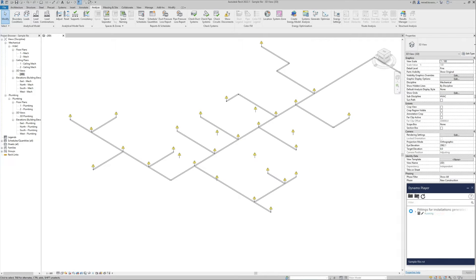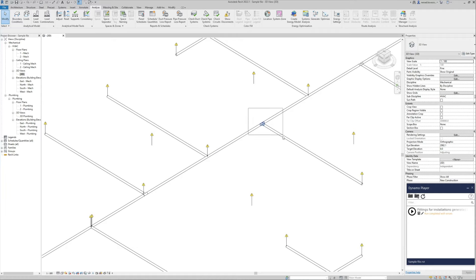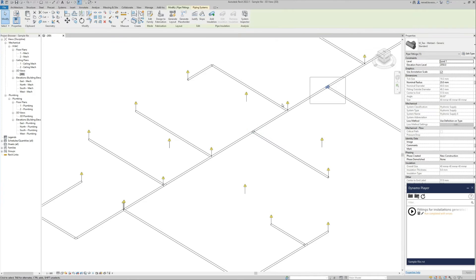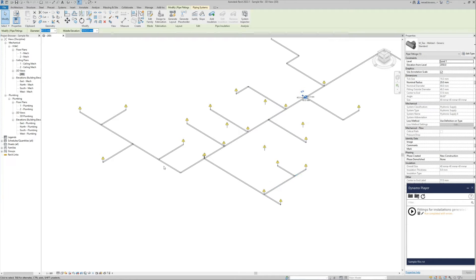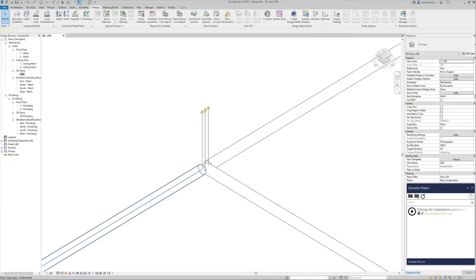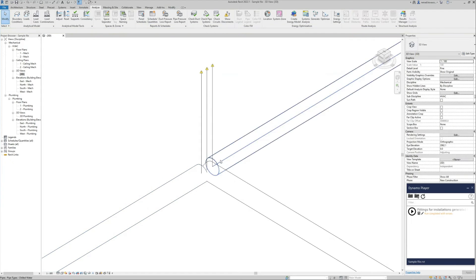Now let's try to add those T-elements. Because of the methodology of how Dynamo finds and connects elements, it can happen that you will need to run this script a couple of times. Inside Dynamo you need to slice this element into a couple of different elements in order to connect them all. So we want to apply the script for the pipes and create T-fittings. You can see that we did create fittings here, here, and all three fittings over here. But over here and here we didn't create them.